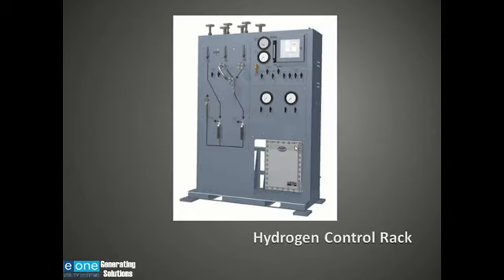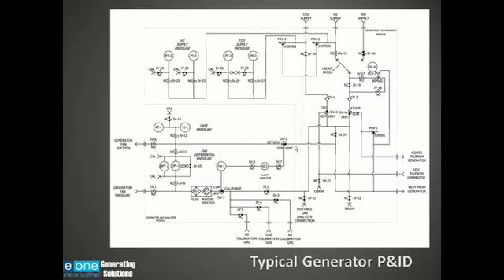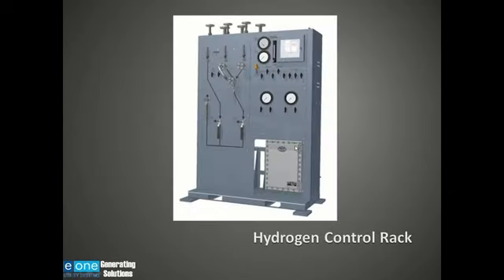This is a hydrogen control rack. This has all the components that we see in this P&ID. So on this rack, we have the gas manifold for putting the gas in and out of the generator and maintaining hydrogen pressure during normal operation. This is that spool piece that will either allow you to put hydrogen in the generator or air in the generator, but not both. This gauge will measure generator fan differential pressure. This one is measuring the case pressure.